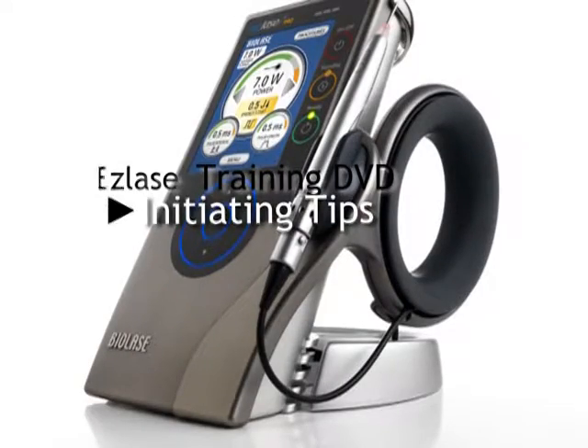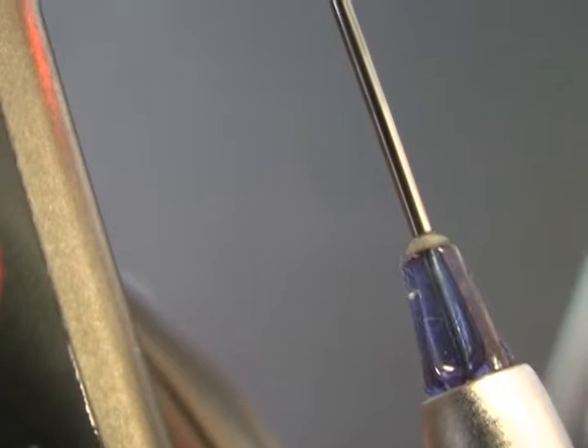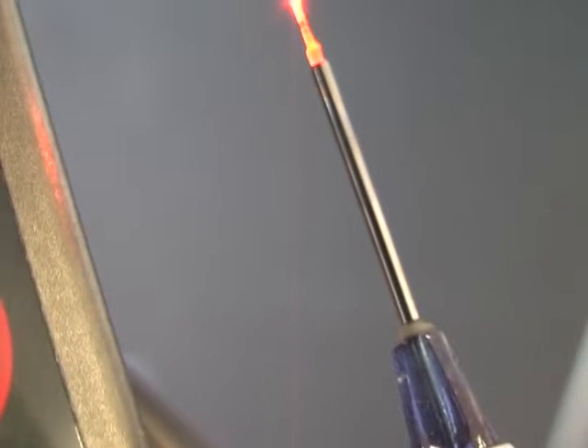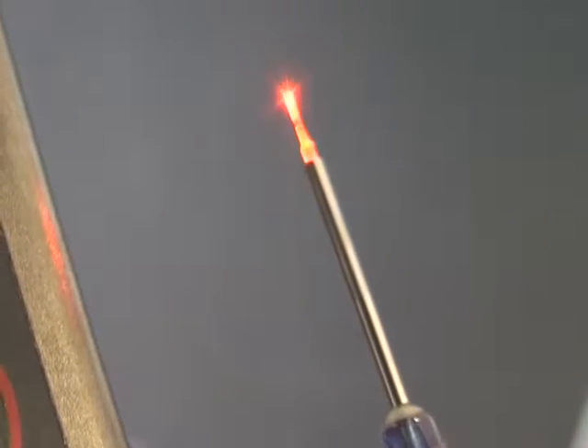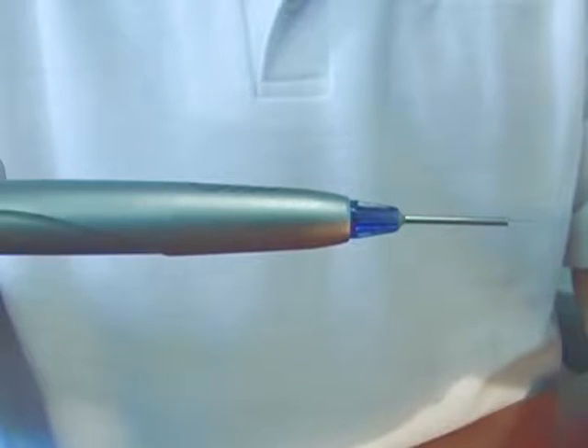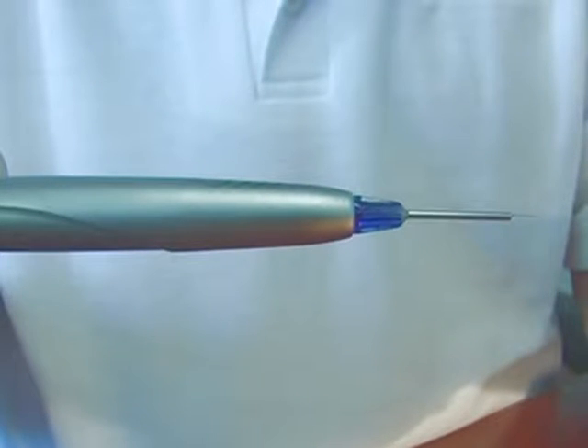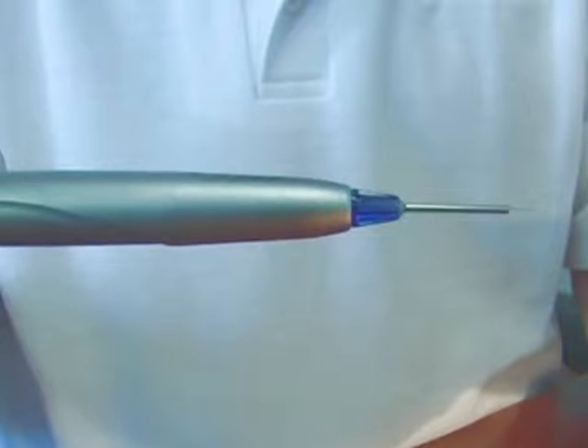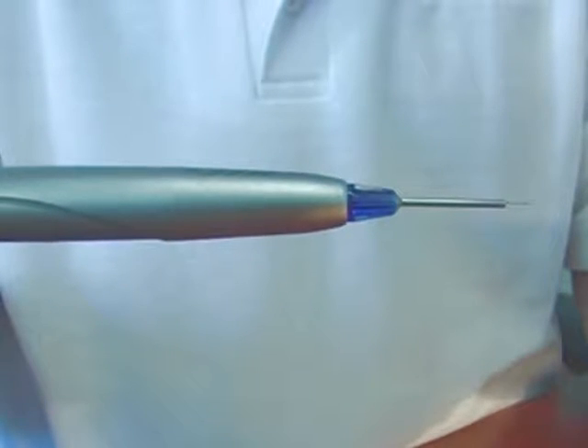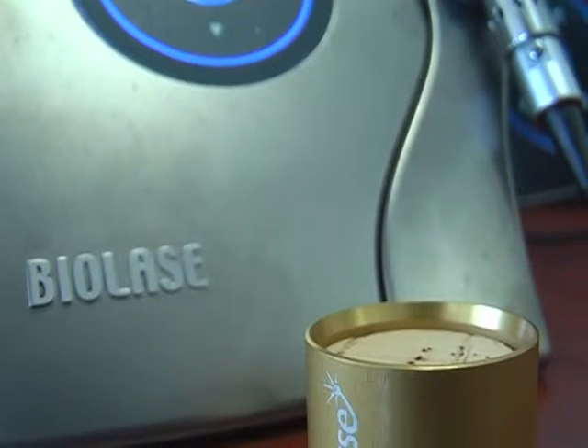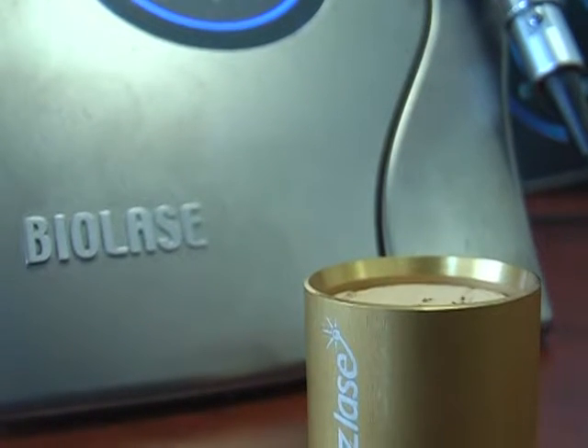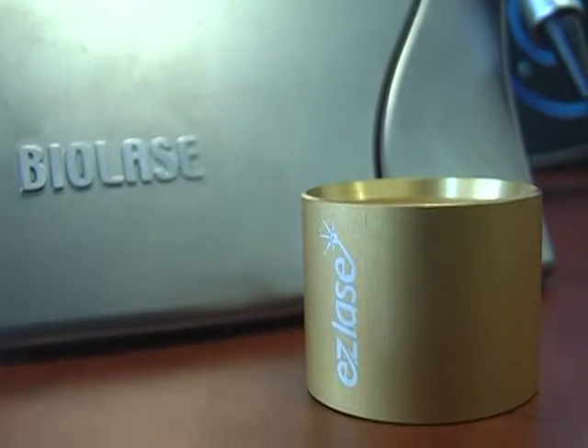The process of initiating a tip involves burning an absorptive material on the end of the tip. After initiation, the end of the tip will heat up as part of the laser energy coming out of the tip is trapped within this material. A new or uninitiated tip will allow the laser energy from the tip to pass into the soft tissue where it will penetrate and be absorbed. The process to initiate a tip is very simple. You will need the Ezlase initiating cork.